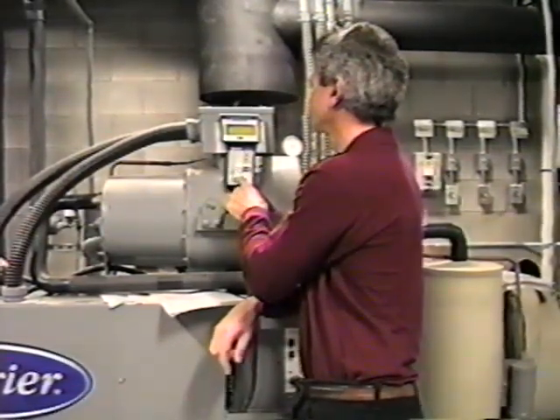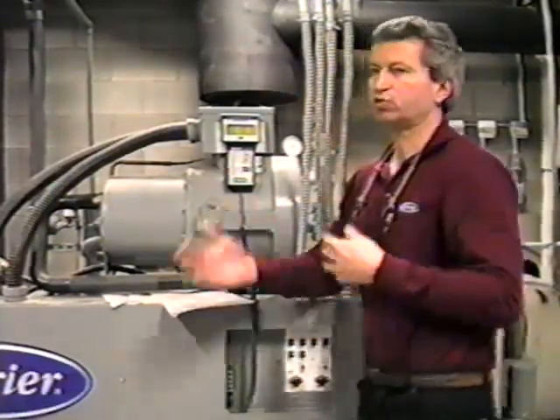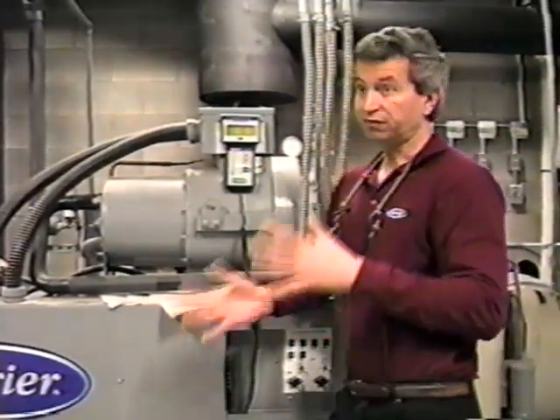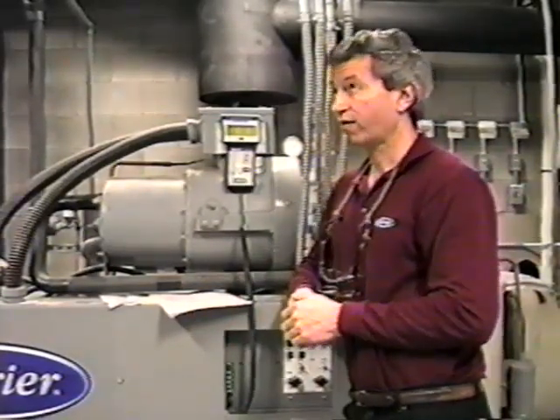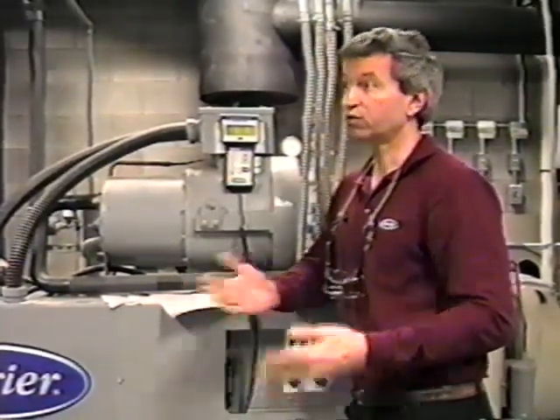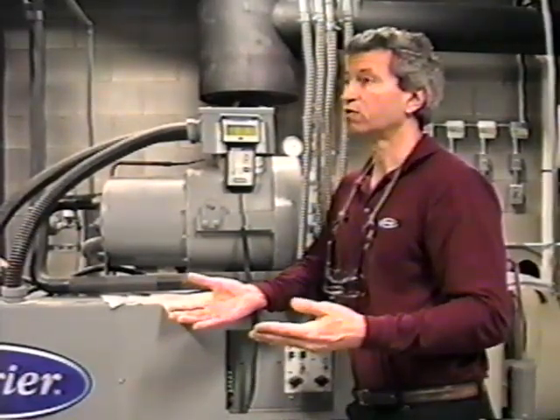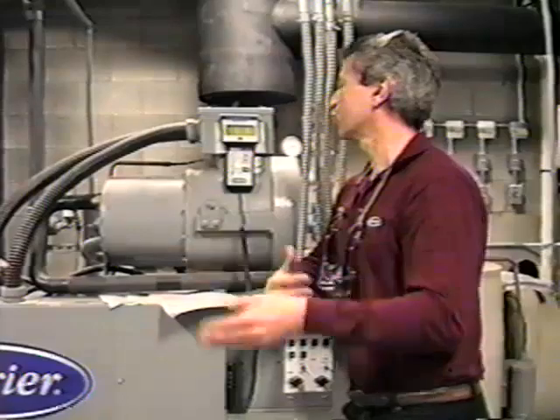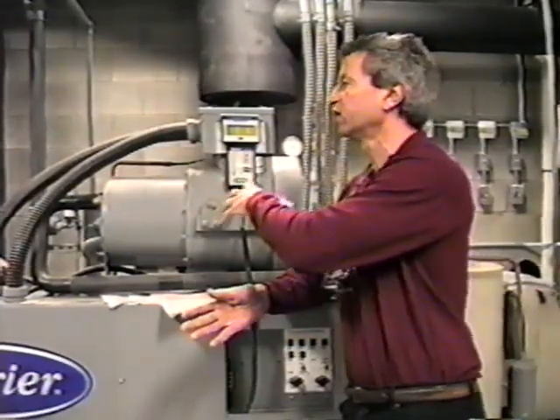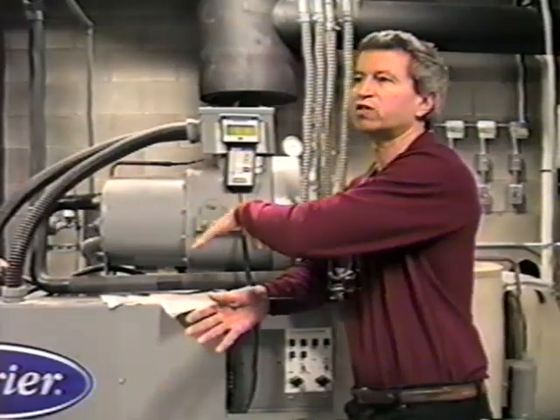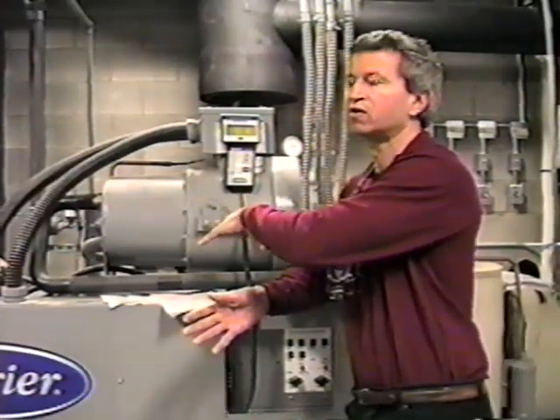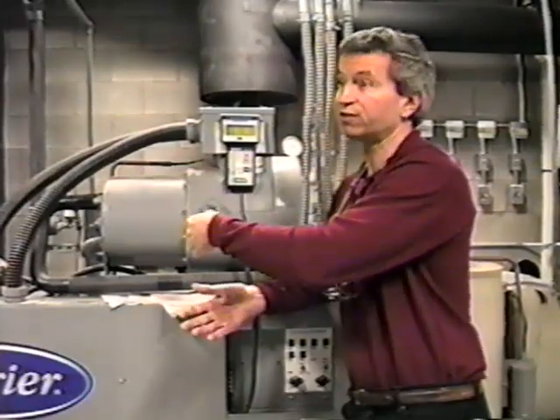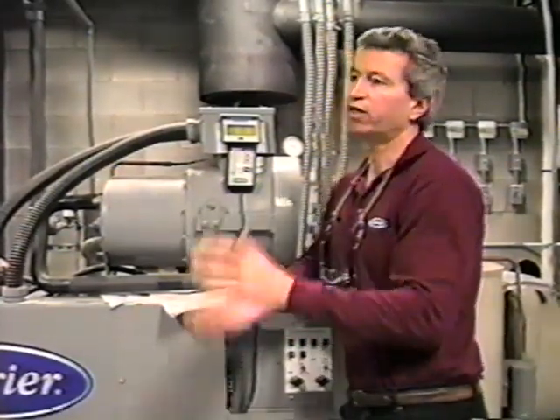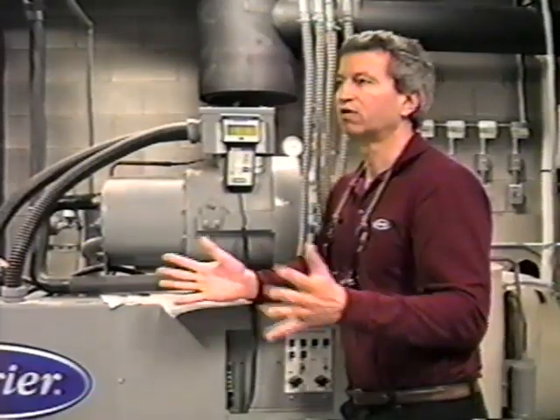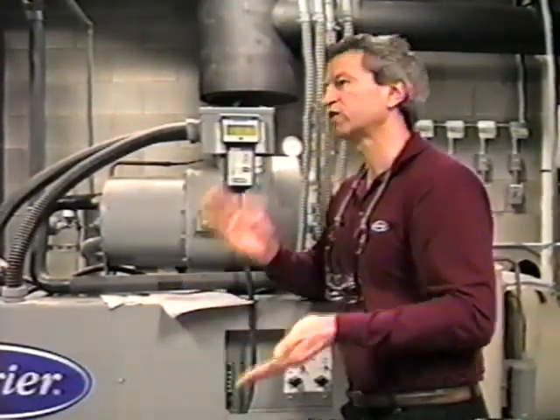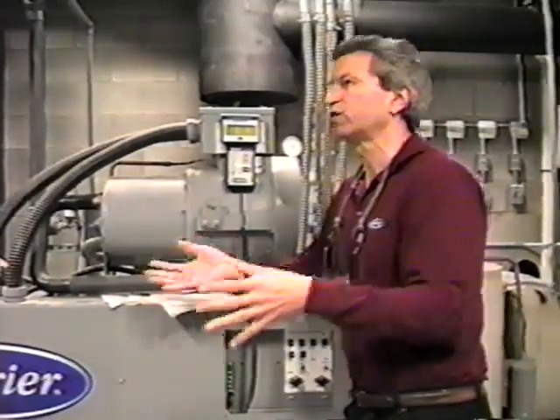Operating modes. There are certain modes that the machine can go into under varying conditions, and it may override the actual capacity control functions of the machine. So if you're set for 15, you may not be controlling exactly to 15 because of some override, some abnormal condition within the machine that it's trying to correct for. And again, it may sacrifice some capacity during that period. And it shouldn't stay in that override mode for a long length of time. It's trying to stabilize conditions within the machine to get everything back to normal.